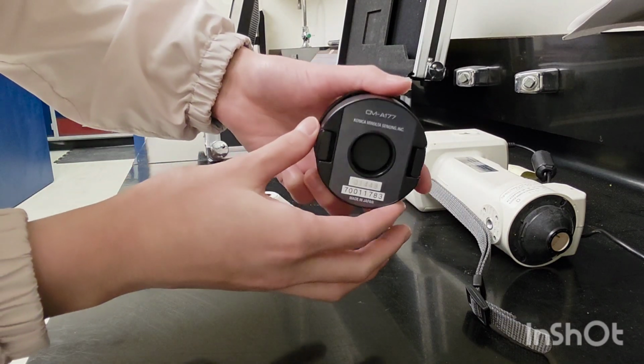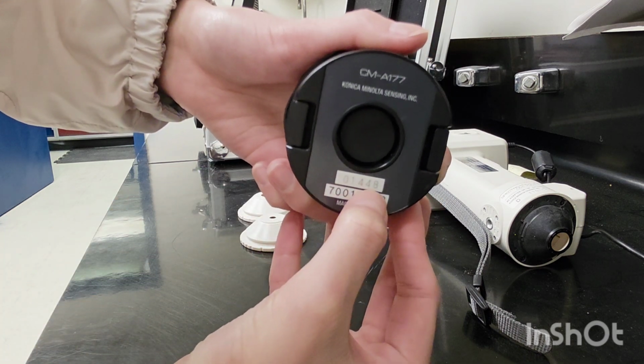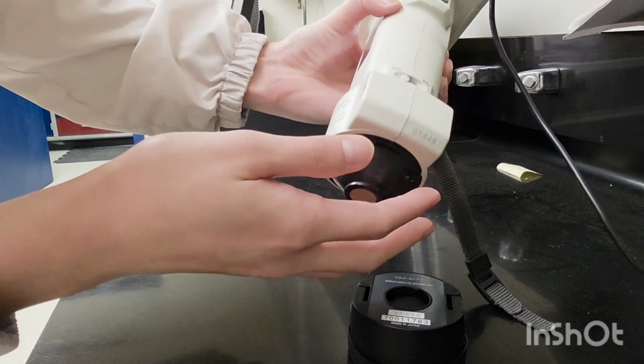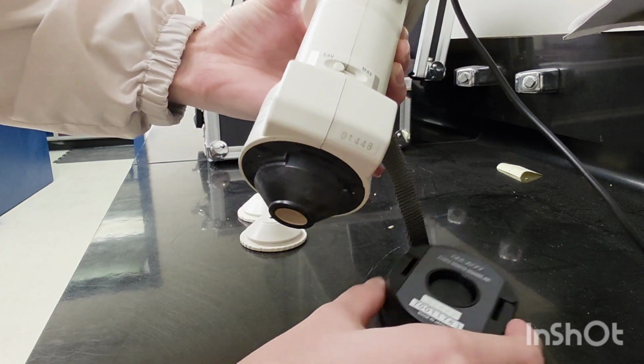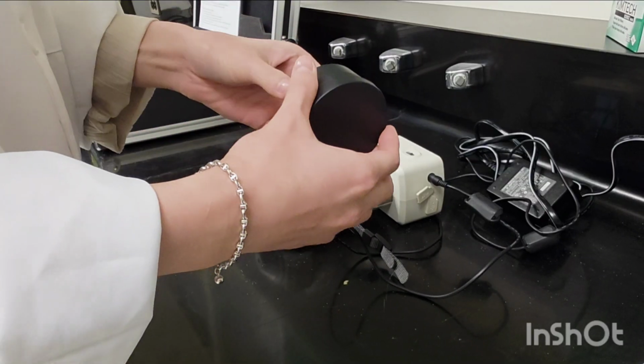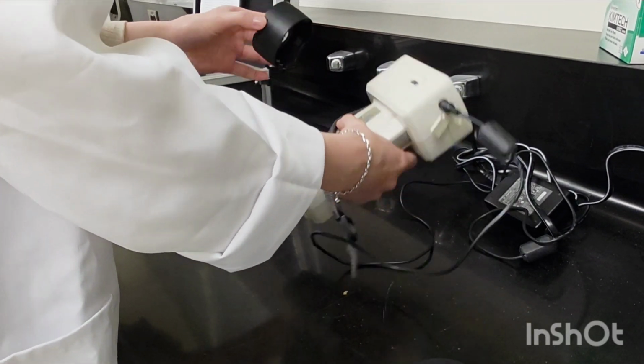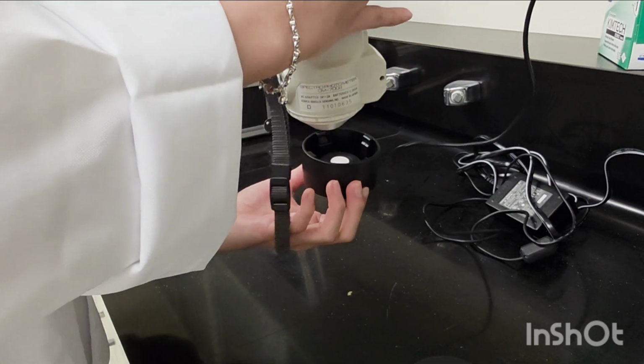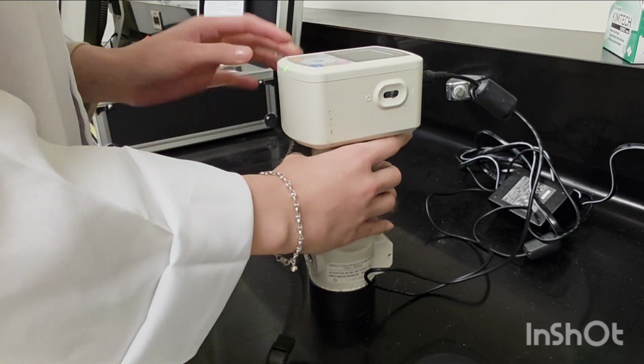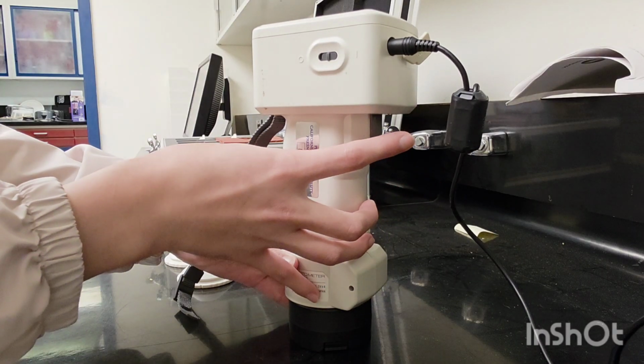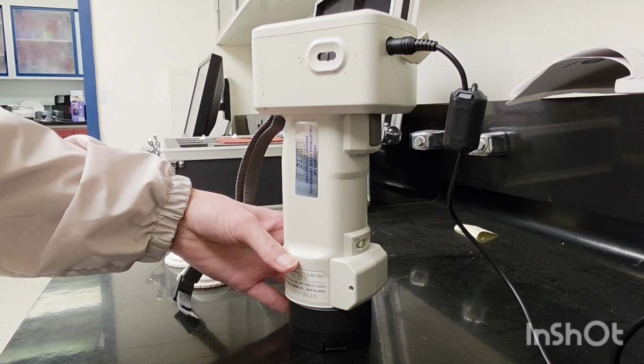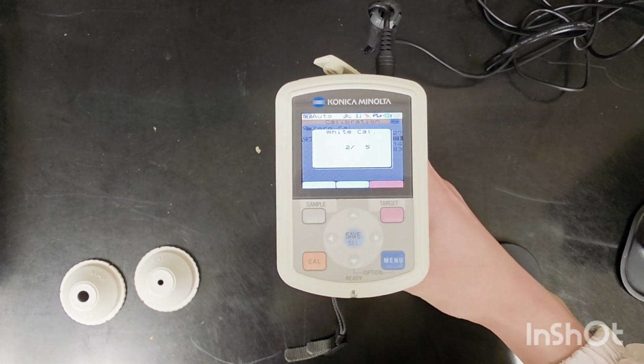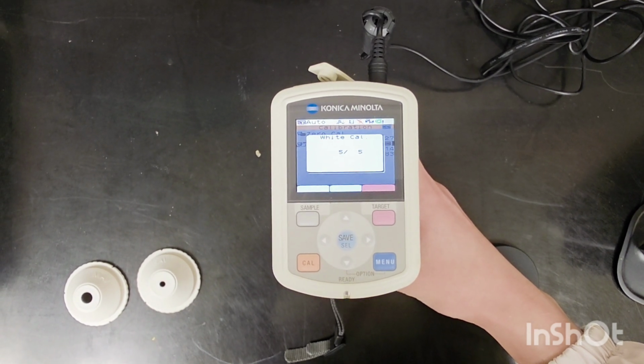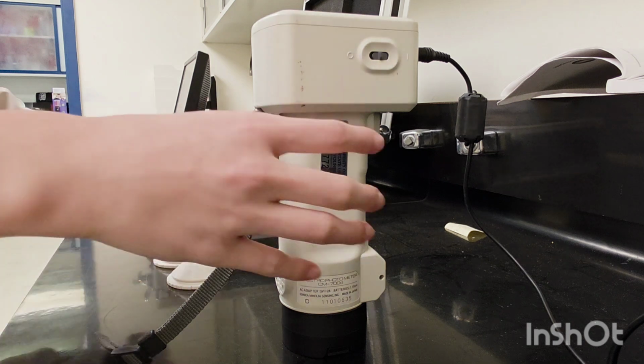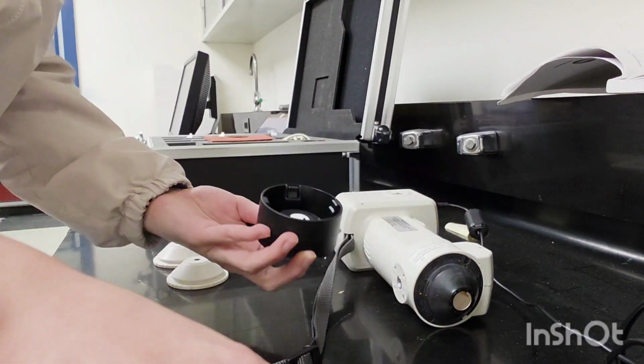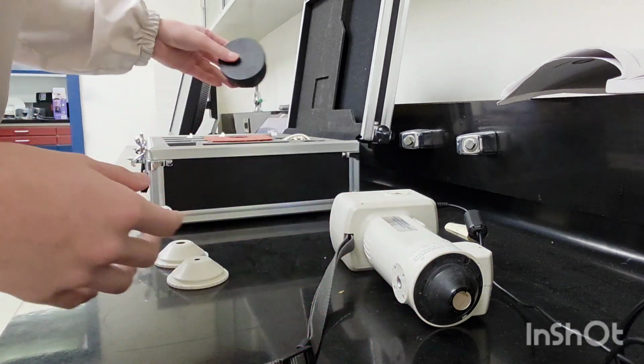To perform white calibration, let's take the white calibration cap and check if the serial number is correct. So we want the serial number on the white calibration cap to match the one on the colorimeter. Once it is correct, let's take off the lid of the white calibration cap, and while squeezing the two locks located on the sides, let's align the colorimeter with the white calibration cap. When it is perfectly aligned and the ready measure light is on, we can go ahead and press the measure button to perform calibration. 5 calibrations will be automatically performed. When calibration is completed, we can take off the white calibration cap, store it back in the box, and the colorimeter is ready for usage.